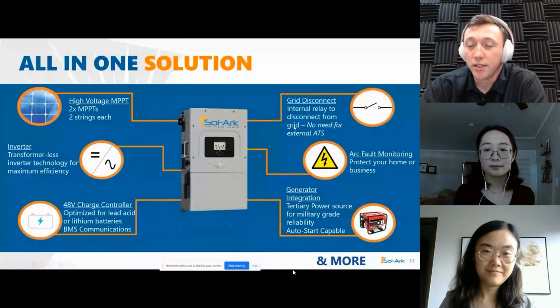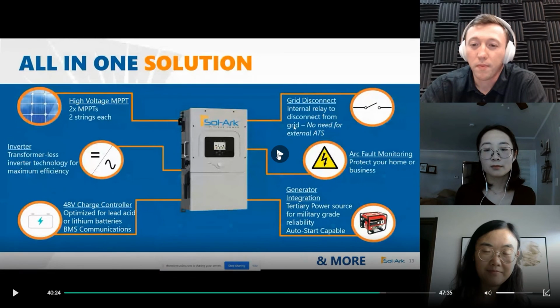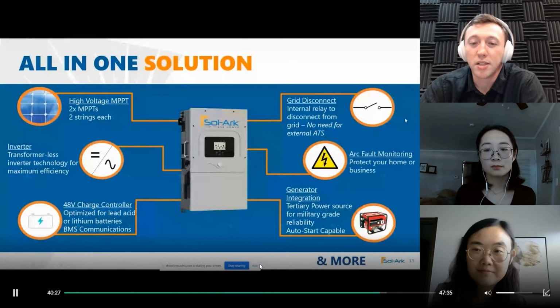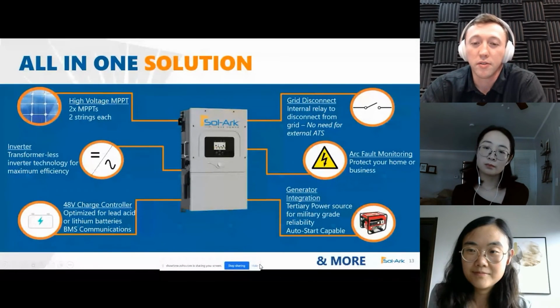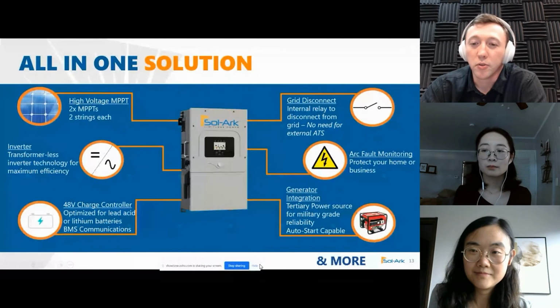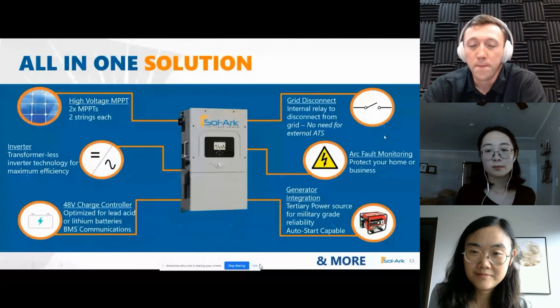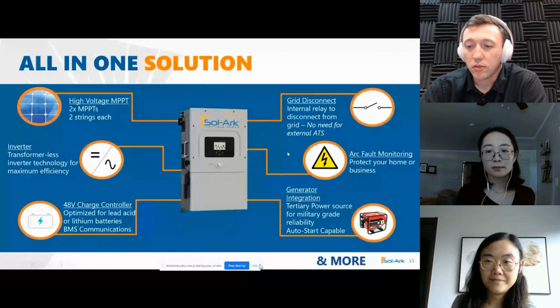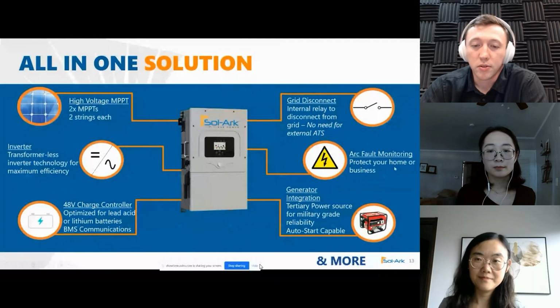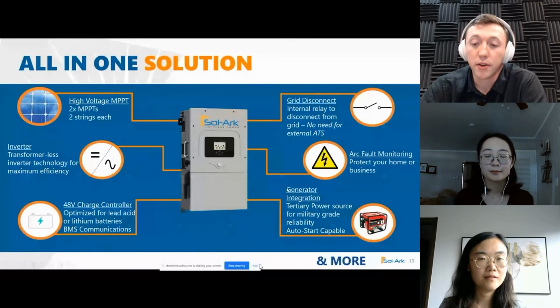We have an internal grid disconnect at our grid connection in each one of our Solark inverters. That means you're going to be able to abide by the UL 1741 code. With this disconnect, we isolate the load output on the inverter, making sure we don't feed back into the grid in a grid outage scenario. So there's no need for an external ATS at that point. We also have internal arc fault and ground fault monitoring to protect your home or business, make sure there's no issues there.